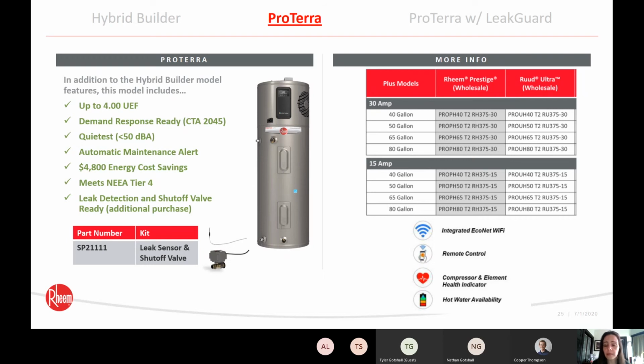Quick note on the 15 amp models: a lot of people ask why you'd even have one. We've seen areas where someone is switching out an old electric water heater that had a 3,000 watt element on 20 or 25 amp service, or switching from an oil fired water heater that already has 15 amp service, wanting a more efficient or environmentally friendly option. Otherwise they'd have to add electrical infrastructure if only 15 or 20 amps are available. Using a 15 amp model lets you use the existing electrical infrastructure.